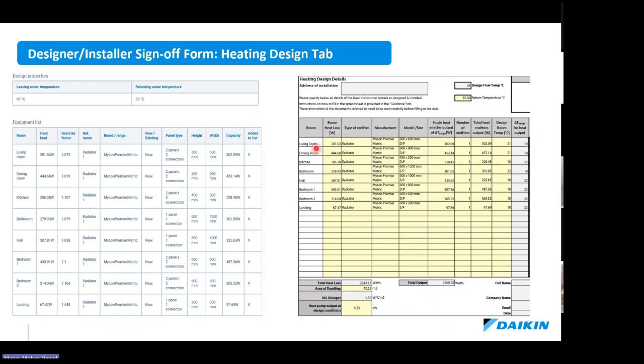And this is where we fill in all the details from the report. So basically you fill in your room names, your room heat loss, type of emitter, the manufacturer name, the model or the size, the output of the radiators, and the number of emitters. And on top here, you would see the design flow temperature and the return temperature. Normally, if it's for radiators, it would be designed at 45, 35 in this case. And then at the bottom, you have the option to enter the area of your dwelling and the heat pump output at design condition. So that's basically the output at -3 and 45 flow temperature.